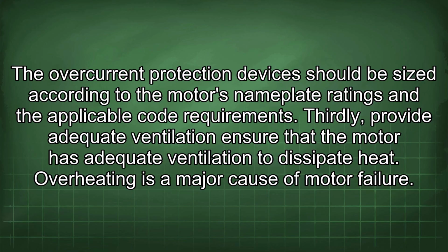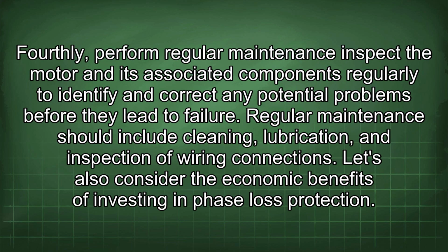Thirdly, provide adequate ventilation. Ensure that the motor has adequate ventilation to dissipate heat. Overheating is a major cause of motor failure. Fourthly, perform regular maintenance. Inspect the motor and its associated components regularly to identify and correct any potential problems before they lead to failure. Regular maintenance should include cleaning, lubrication, and inspection of wiring connections.